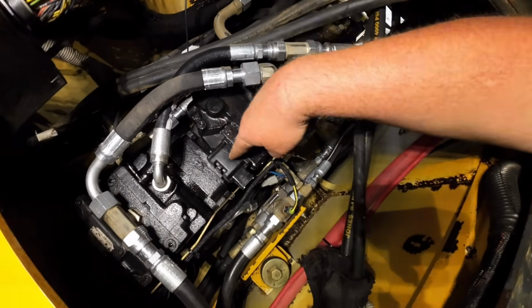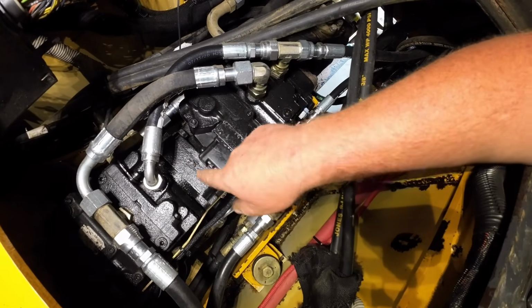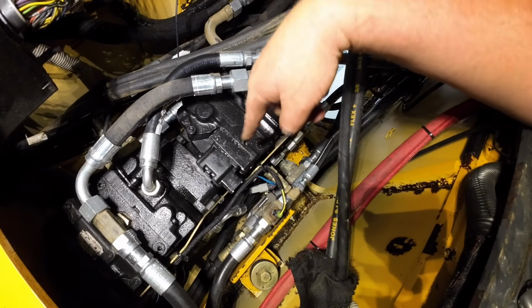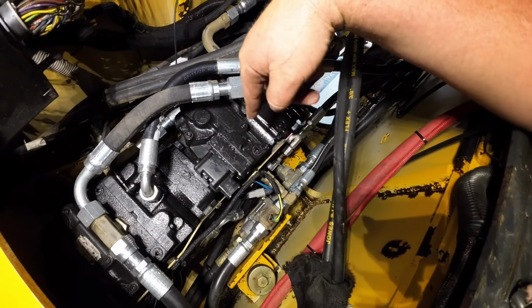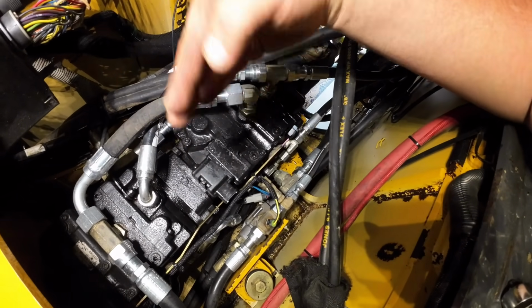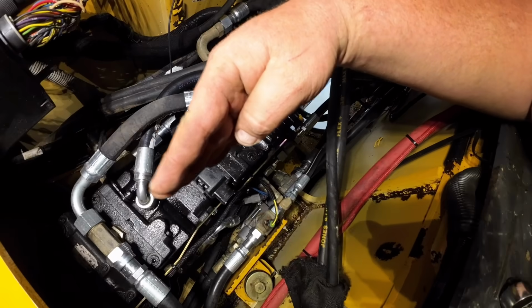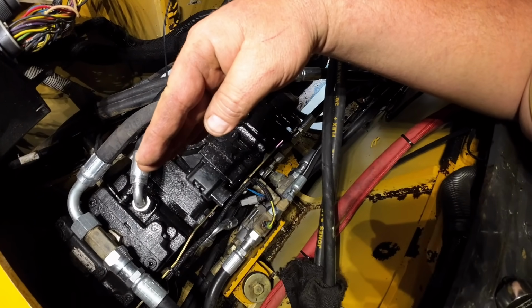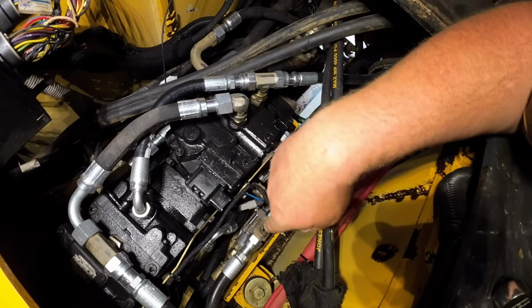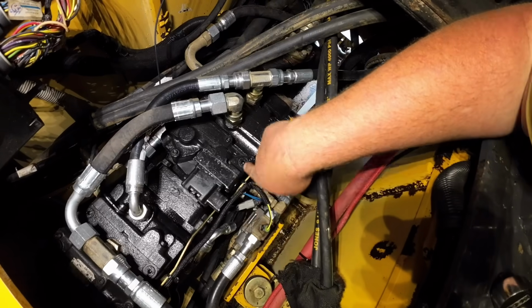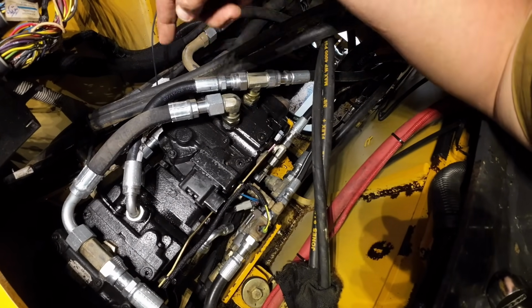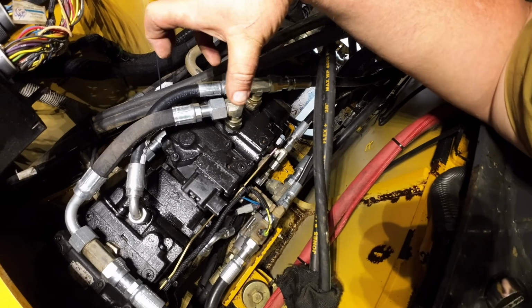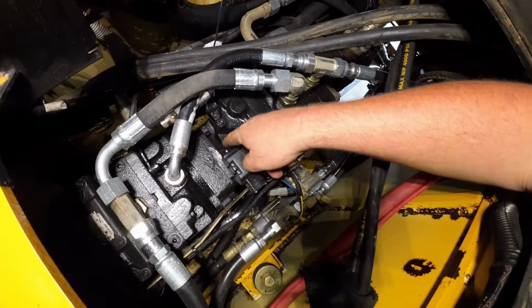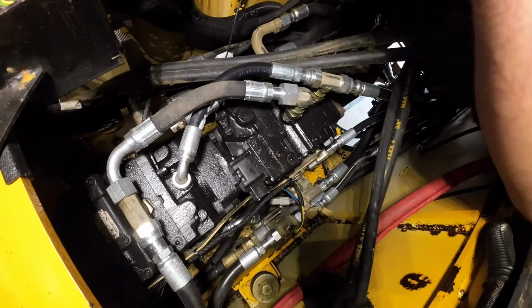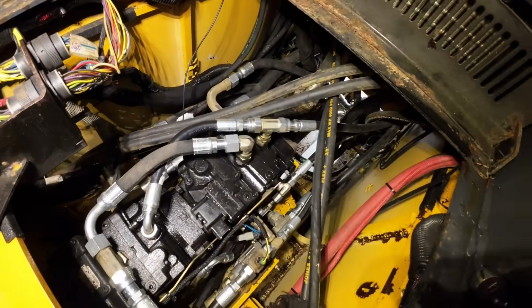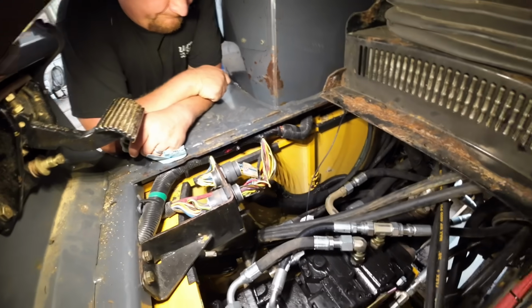I'll try to show you. So there's two wires going into this electric spool. It moves a spool in here which tells the pump which way to go, forward or backwards. That spool has to be balanced in neutral. If it's got more pressure on one side or the other, it's going to creep one way or the other. So we're going to pull this plug out, that plug out, throw our gauges in there, and if it's off, we can pop this screw out right here and adjust that pressure. We have to do it with the dozer running, of course, and it's nice and hot.